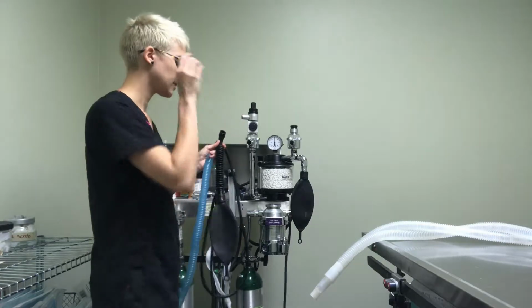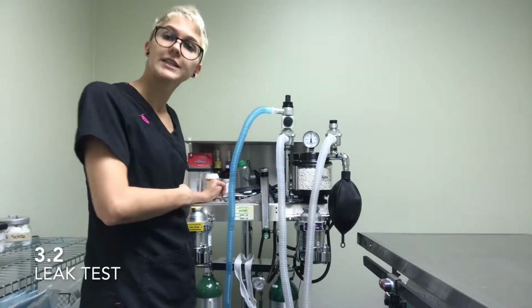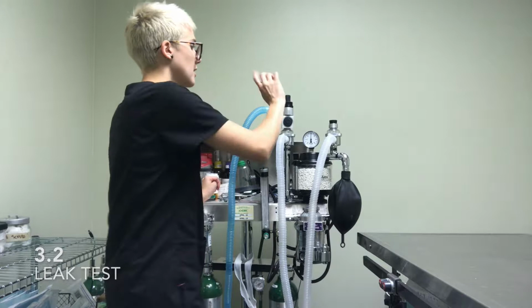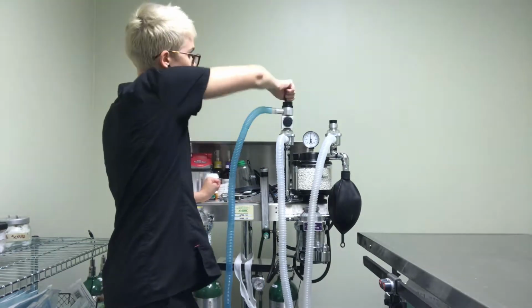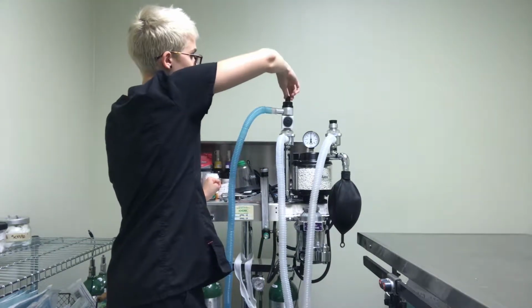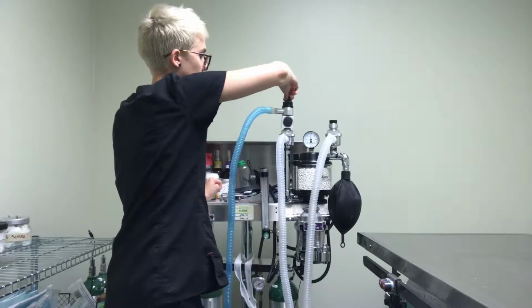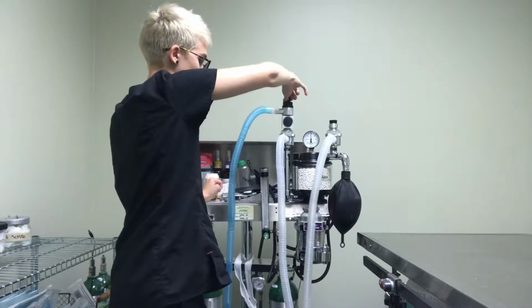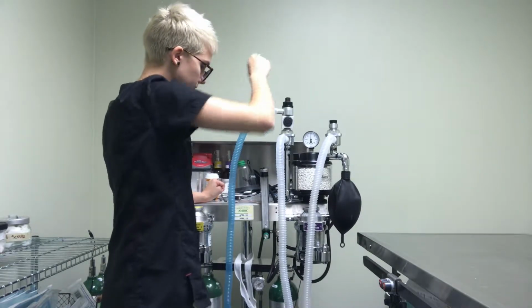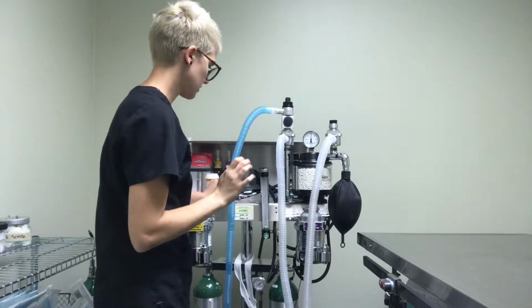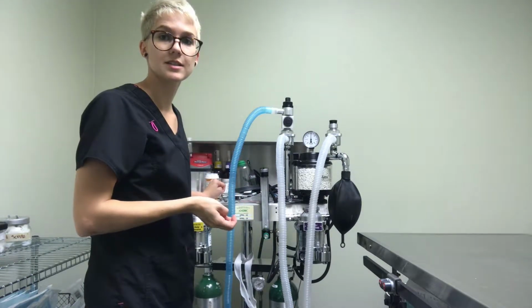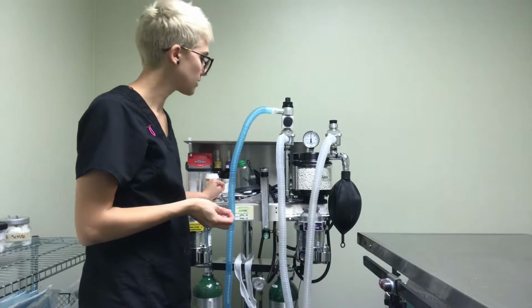I'm going to demonstrate a leak test on the anesthesia machine. First thing I'm going to do is close the pop-off valve. I don't want any place for air to be able to exit, so if there is a leak, I'll be able to notice it.